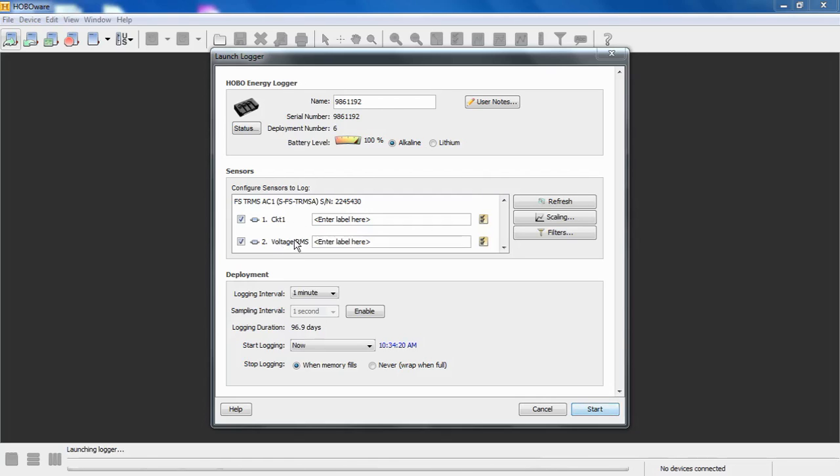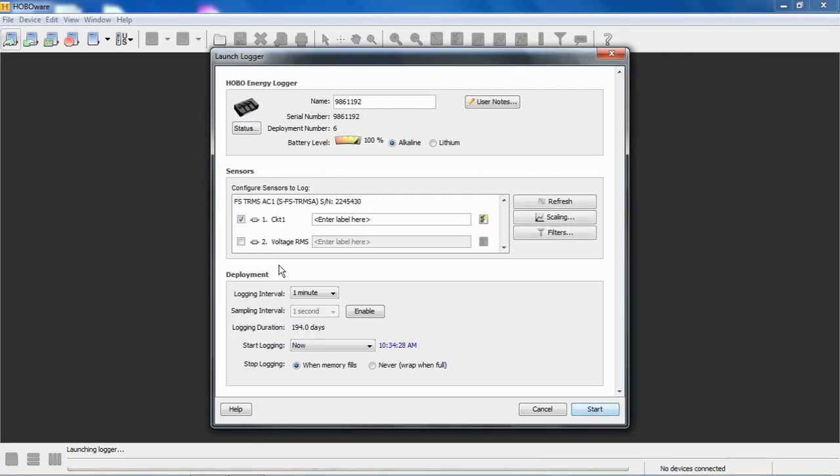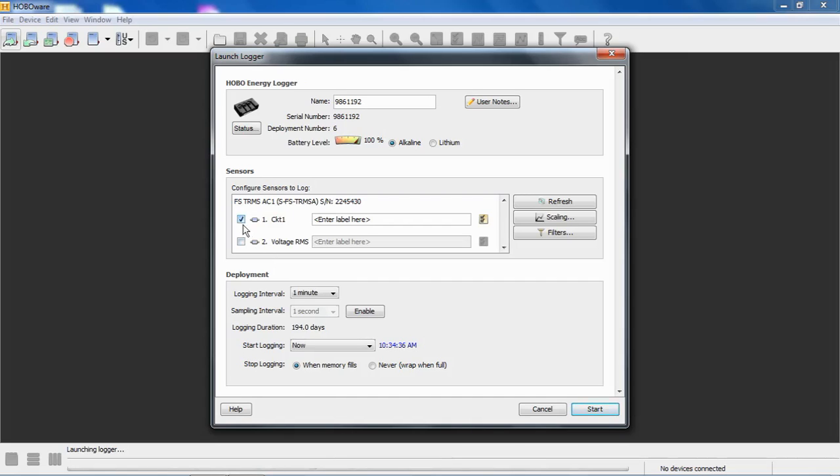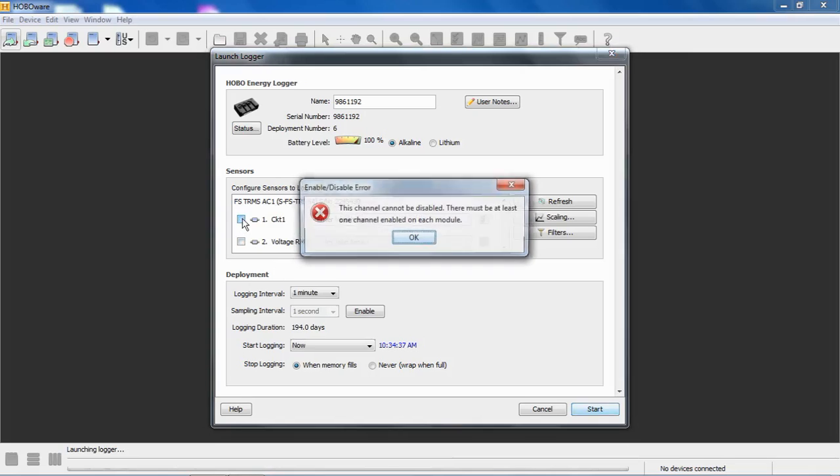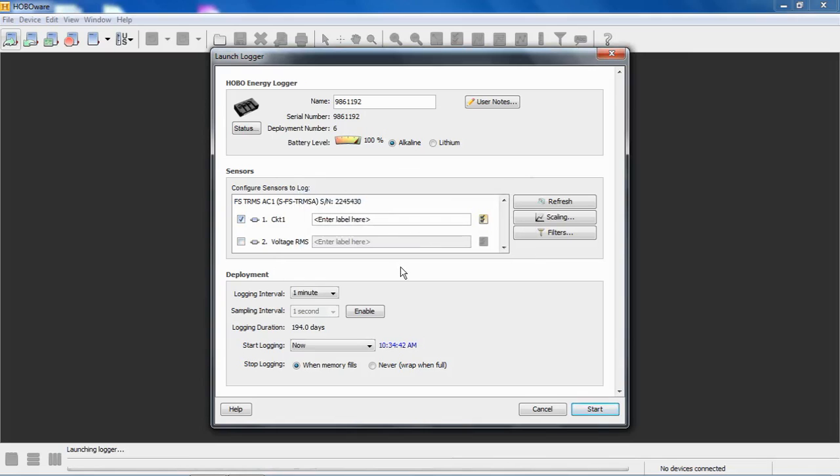We can disable the other channel if we're not using it. Just by unchecking it, HoboWare goes out, scans this sensor bus, and reflects that this is turned off. You can only turn off one of the two available channels in your module. Otherwise, you get this error message. It says at least one channel must be enabled. I'm not sure why you wanted to disable two channels if you can just remove the module. But anyway, you can only disable one.